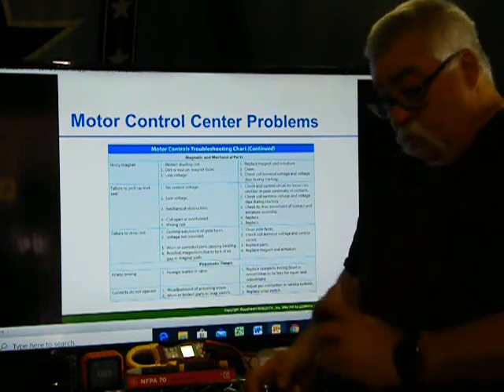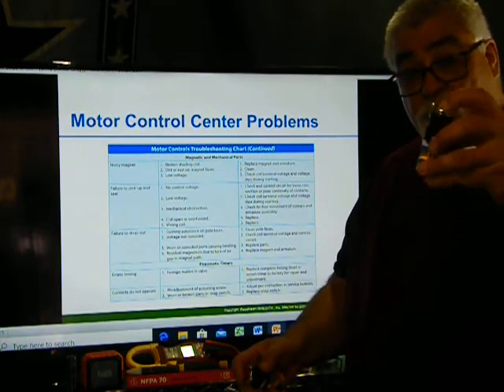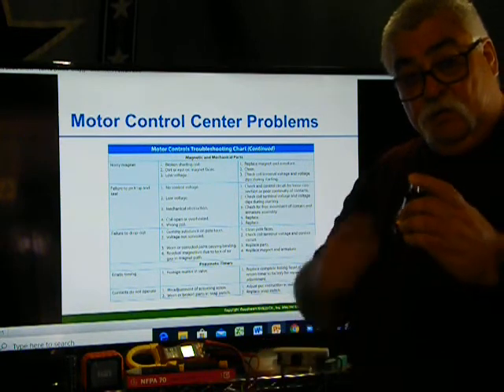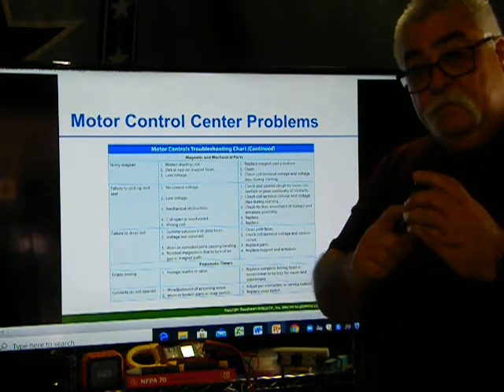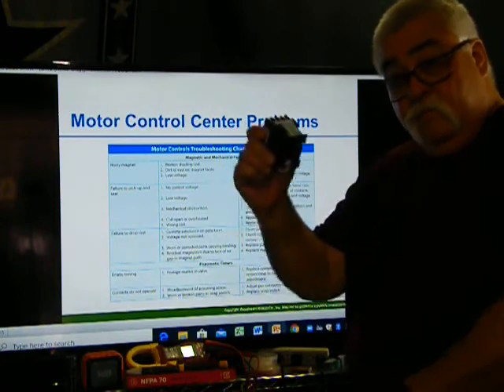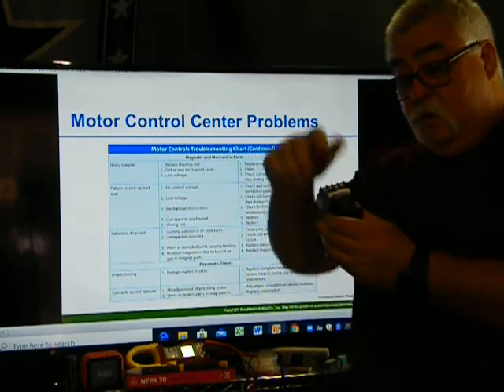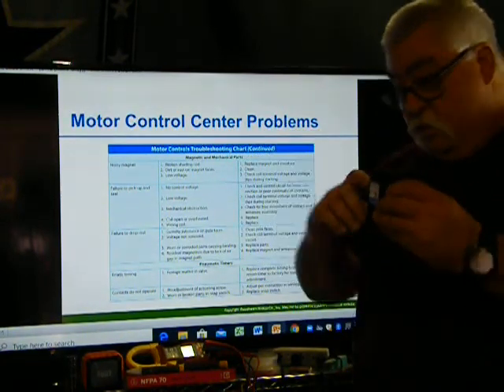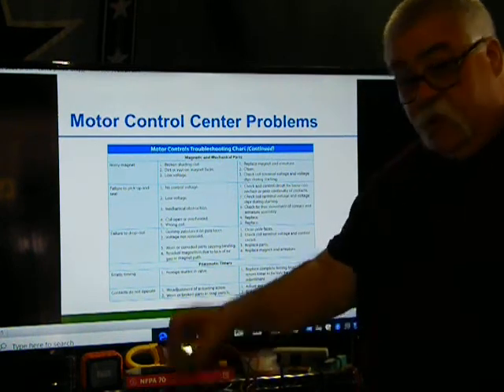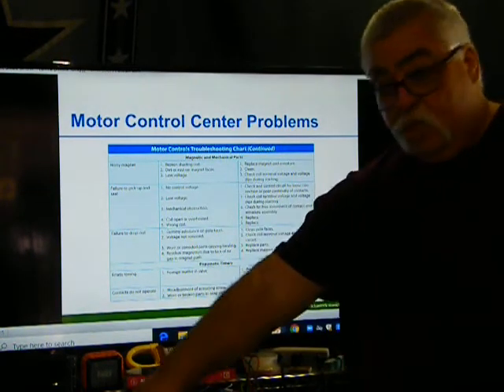Okay, your start button. You hit the start button, nothing happens. The motor doesn't come on. You check that you have voltage here first. Then you go to the contactors. Is voltage coming to the contactor? Input voltage coming in. This is your controls. Okay, you have different relays along the line. Check your relays. Make sure proper voltage is there.